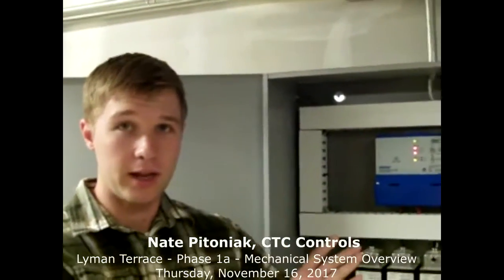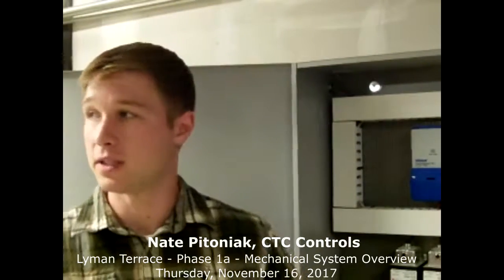Can you change the temperature at which these pumps turn off? Yes. But I saw Joe shaking his head. Yeah. There is a warm weather shutdown on the boilers as well. There's both. If you change it here, you're going to want to make sure you change it there, just so you won't have a situation where your pumps are off, but your boilers are running. Oh. Cause a couple headaches.